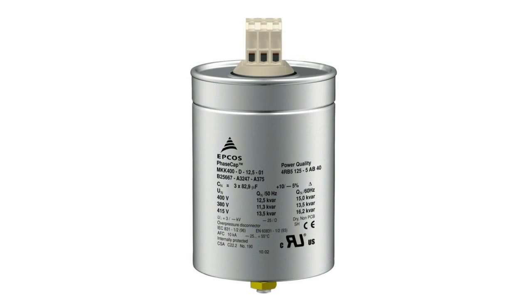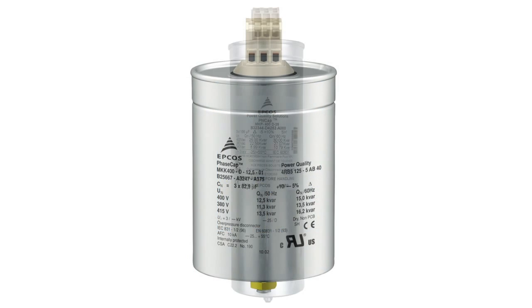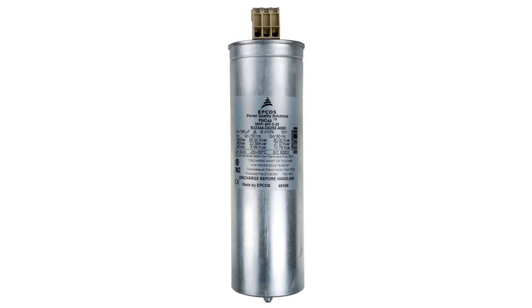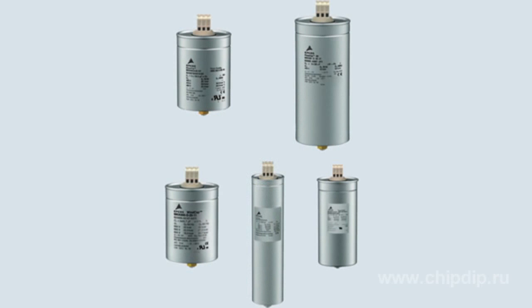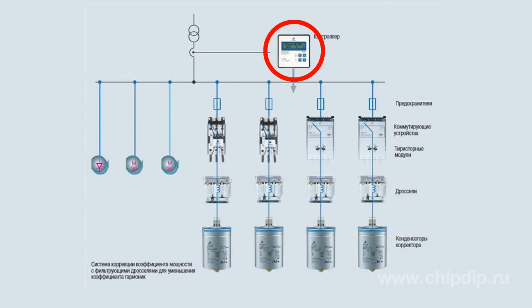Capacitors for power factor correction circuits must be able to sustain the high lift-off currents that occur in switching capacitors. The value of lift-off current can exceed the rated value by as much as 100 times. If the capacitors in the bank are connected in parallel, the lift-off currents become even higher, at times exceeding the rated value by 150 times. This happens because the lift-off current flows not only from the feed circuit, but from the capacitors connected in parallel as well.